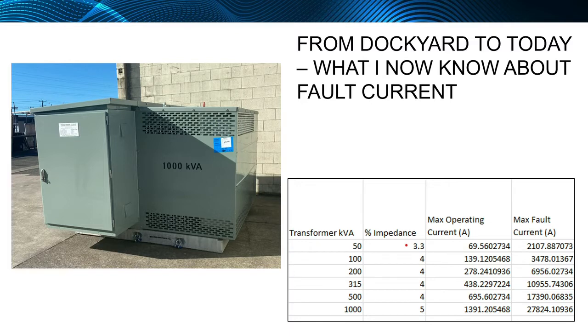Close to 28 kA can be delivered by a 1000 kVA substation. And there's a lot of them around, particularly around the cities. A 500 kVA, which is very much around everywhere else as well, delivers 17 kA. So these are very high fault levels of current that can come through these substations.